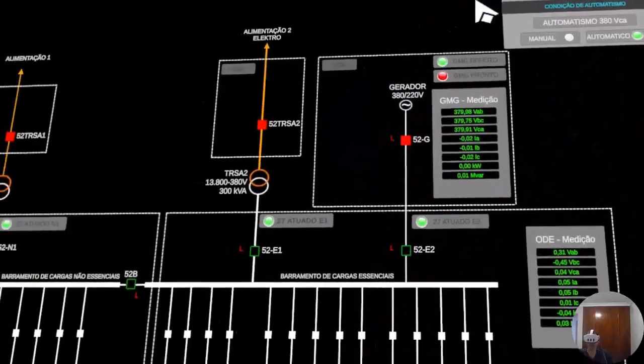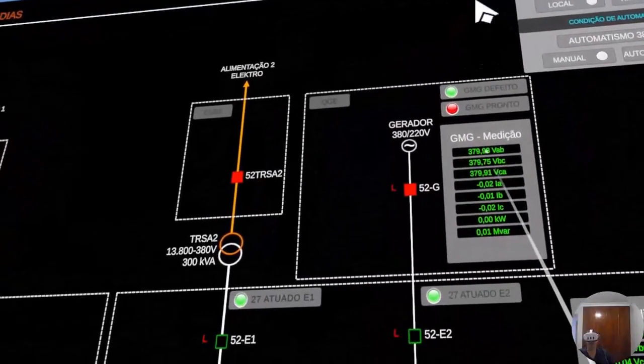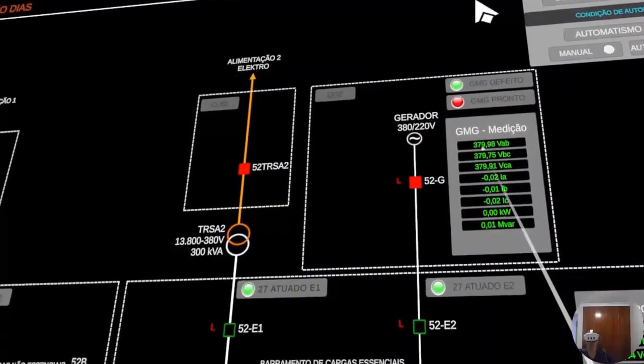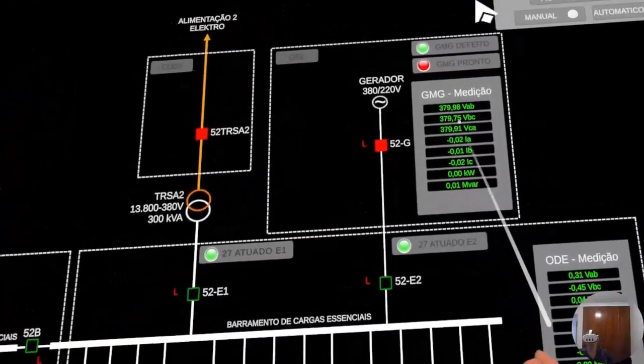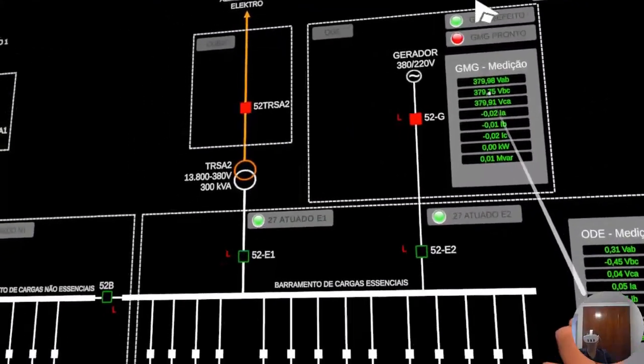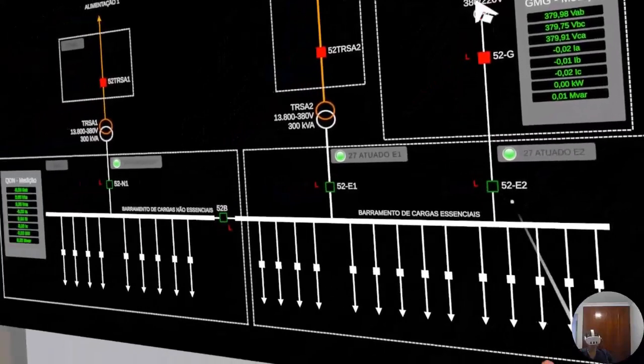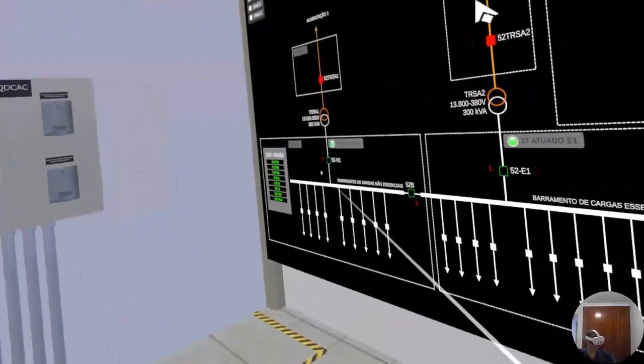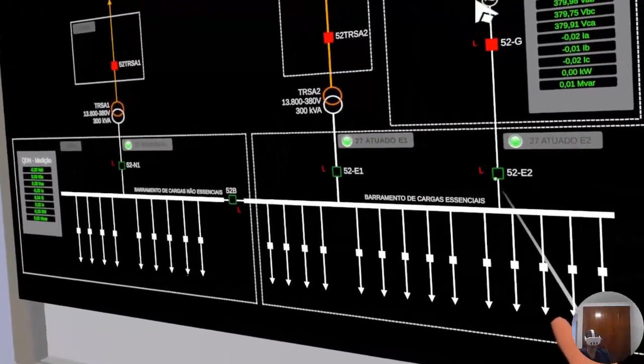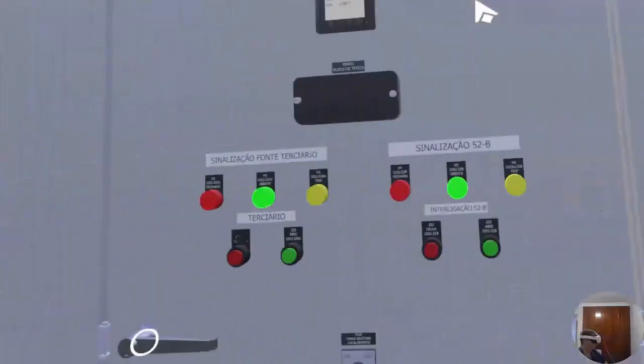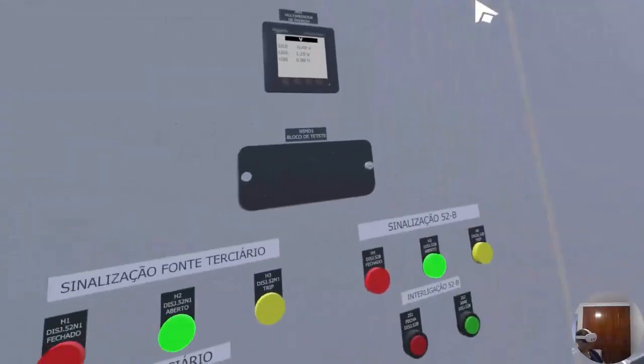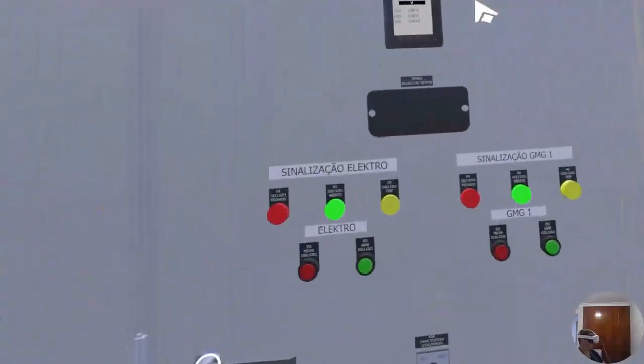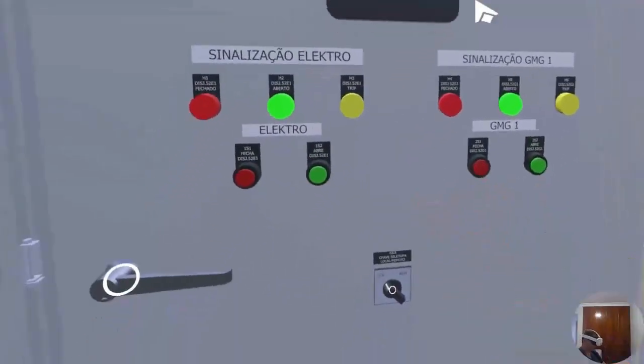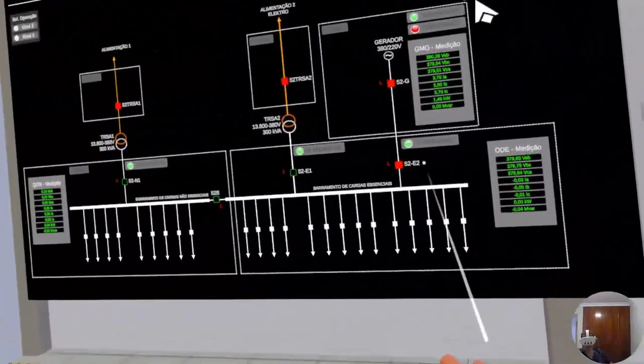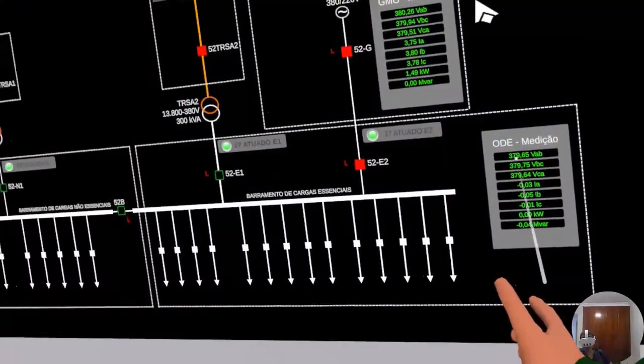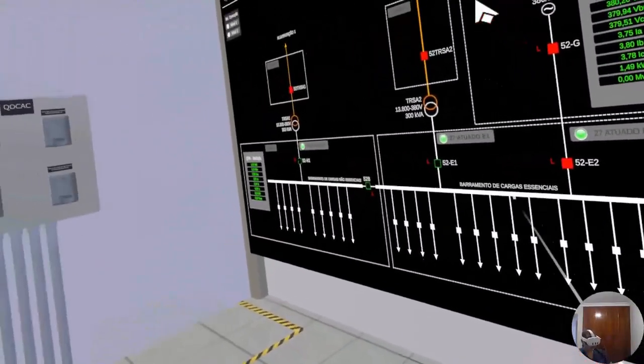What do we have here? 380 volts here on my power generator, which is the output voltage. So I have the circuit breaker closed, 380 volts. 0 here, 0 here. I need to bring back the essential loads. I'm going to close this circuit breaker here. The emergency one. This one. Closed. Now I have 380 here on the essential loads.